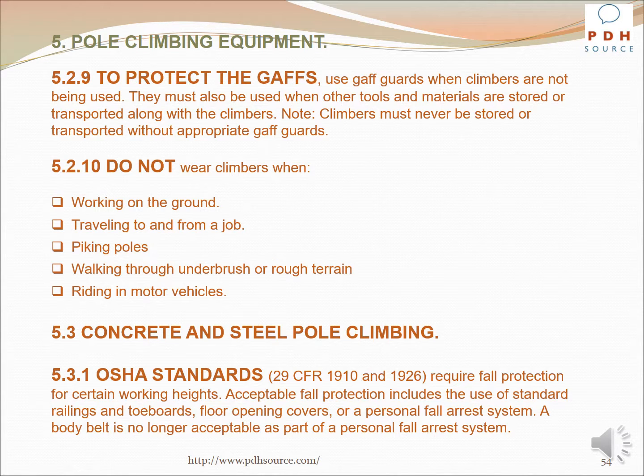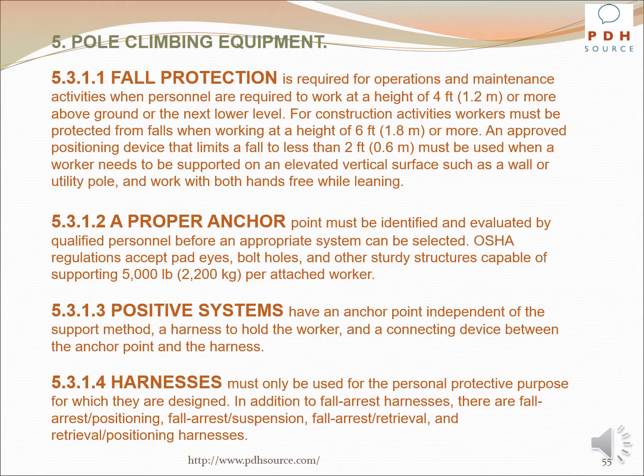With regard to concrete and steel pole climbing, OSHA standards 29 CFR 1910 and 1926 require fall protection for certain working heights. Acceptable fall protection includes the use of standard railings and toe boards, floor opening covers, or a personal fall arrest system. A body belt is no longer acceptable as part of a personal fall arrest system. Fall protection is required for operations and maintenance activities when personnel are required to work at a height of 4 feet or more above ground or the next lower level. For construction activities, workers must be protected from falls when working at a height of 6 feet or more.